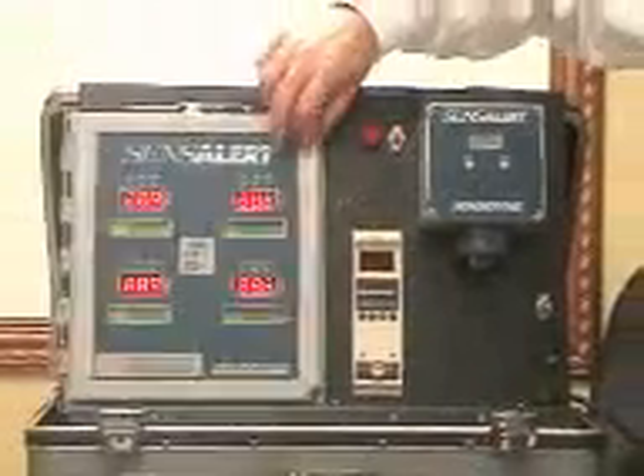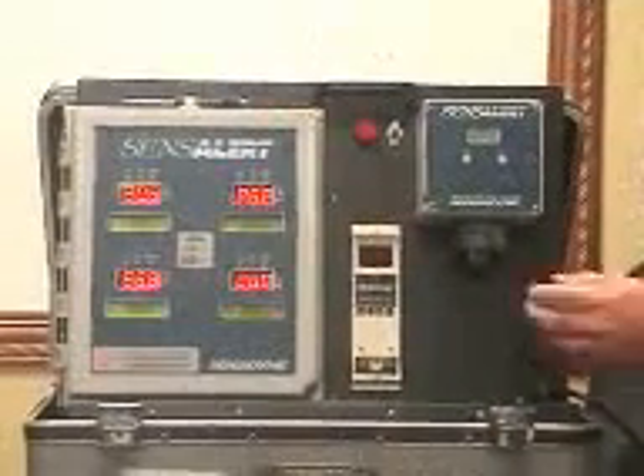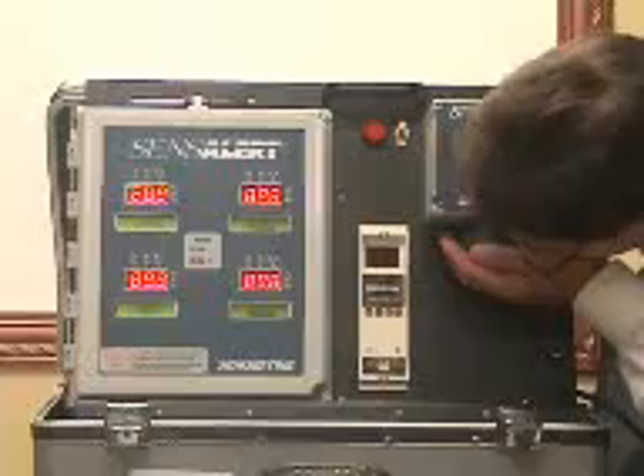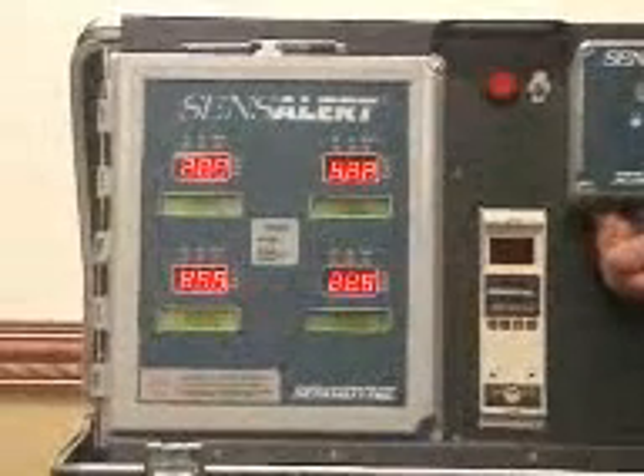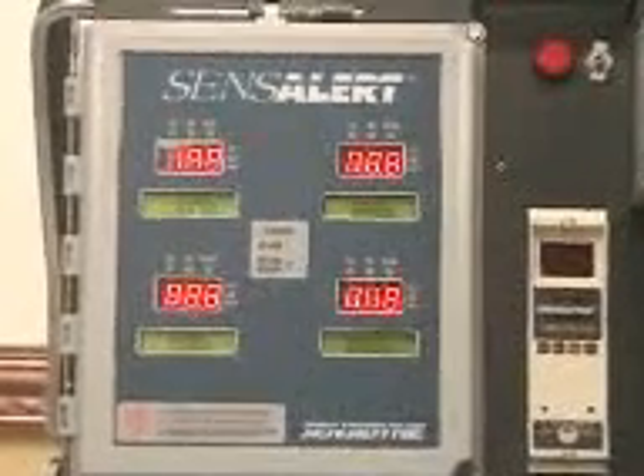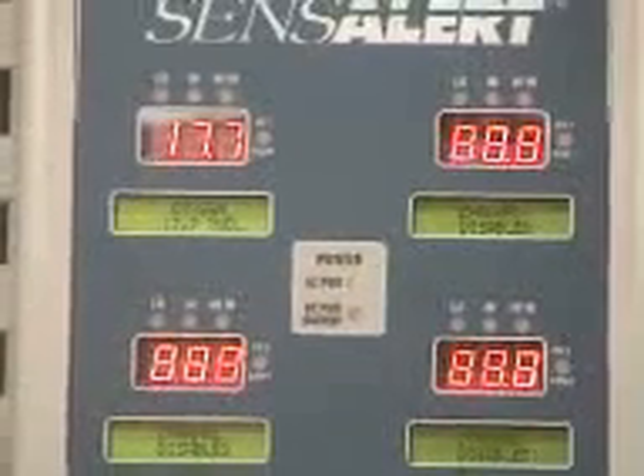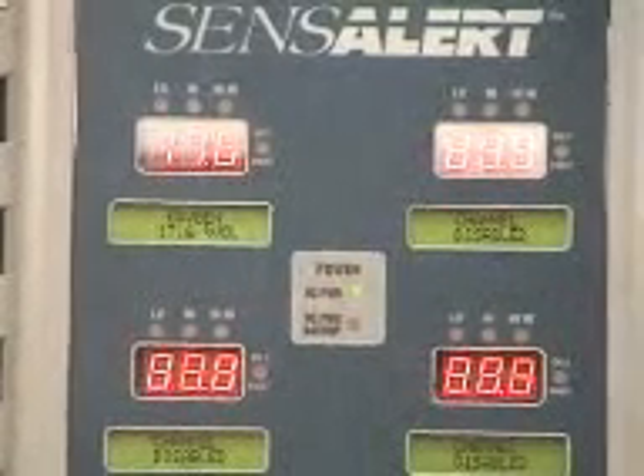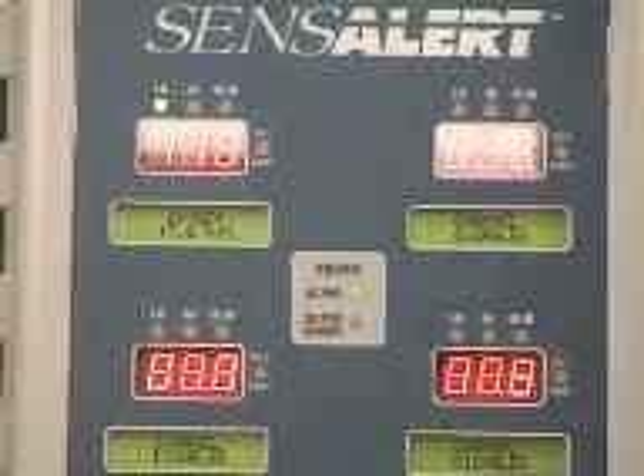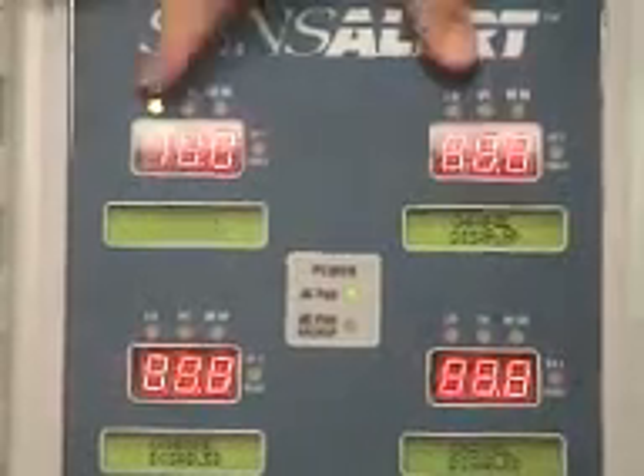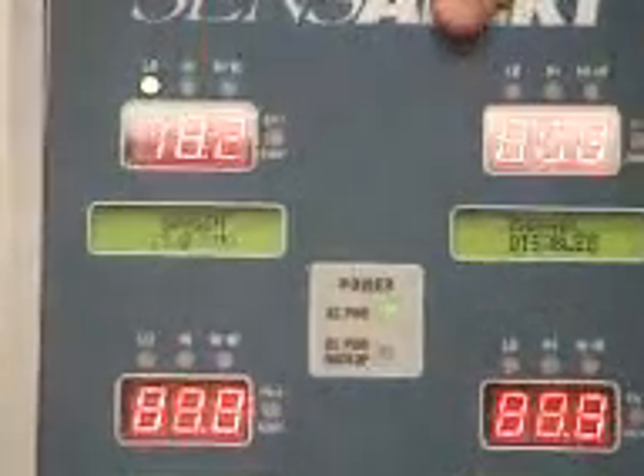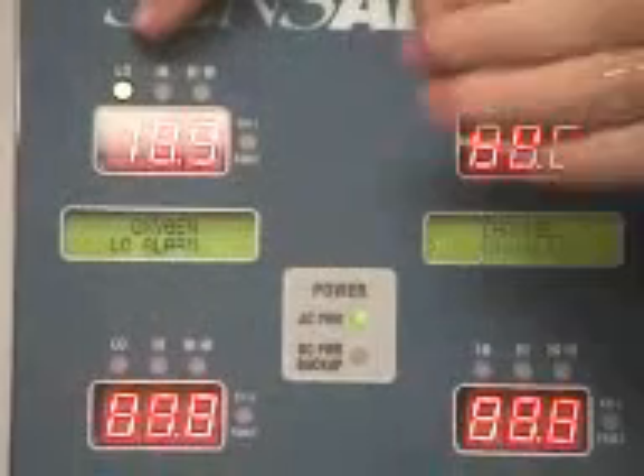And then I'm going to cup my hands just like we did with the portable gas detector. And reduce the concentration of gas on it. And it's going into, you should see an alarm light lit up. There it is, the low alarm, low and a high. No, it's not a high, it's just the direction I'm seeing from the side here. I can see the low.